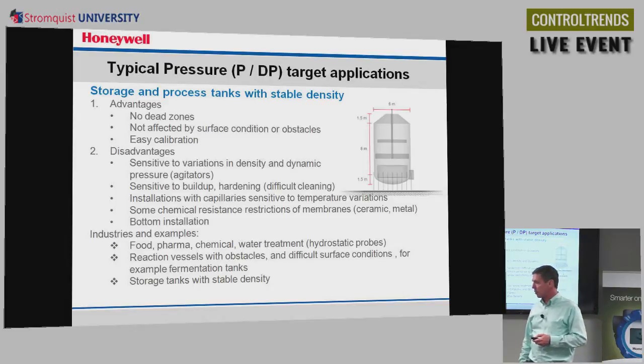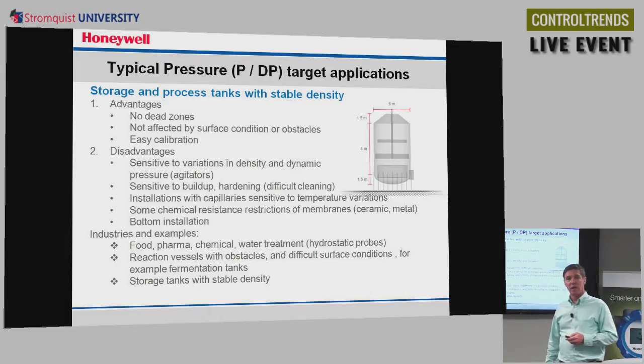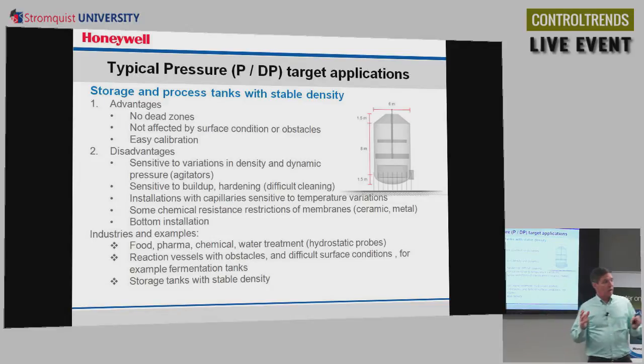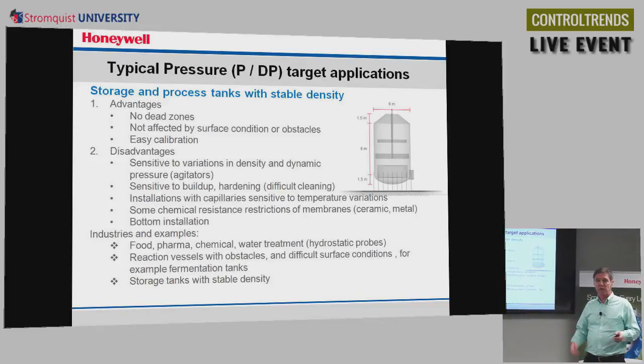There can be some chemical resistance restrictions on the membranes, and this is a bottom installation. What I mean here is that if somebody says, hey, I want to make a level reading on this tank, the customer is going to have to empty the tank to install the pressure diaphragm at the bottom. So it's not always convenient to have to empty out a tank.